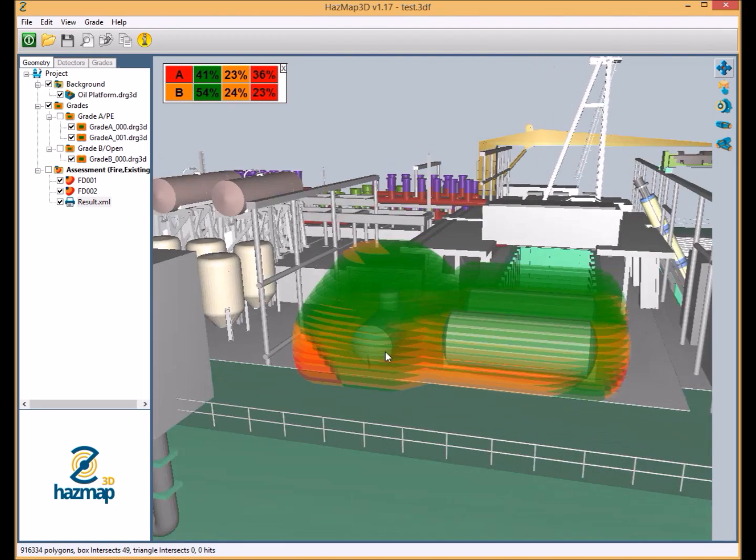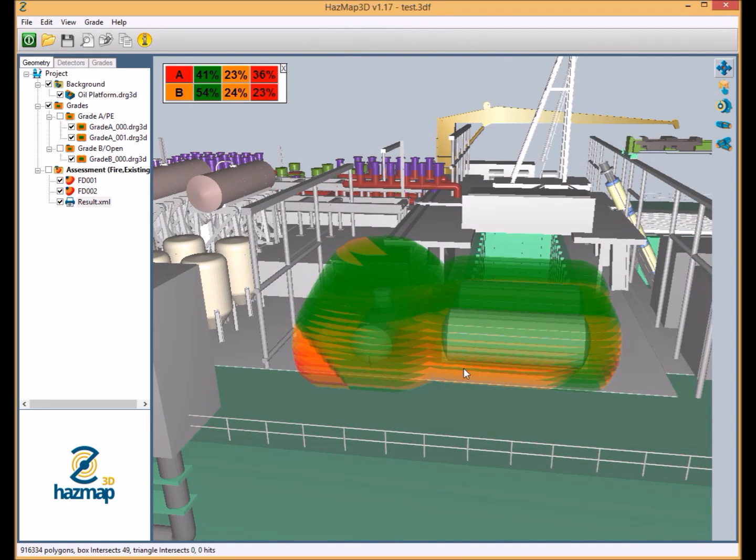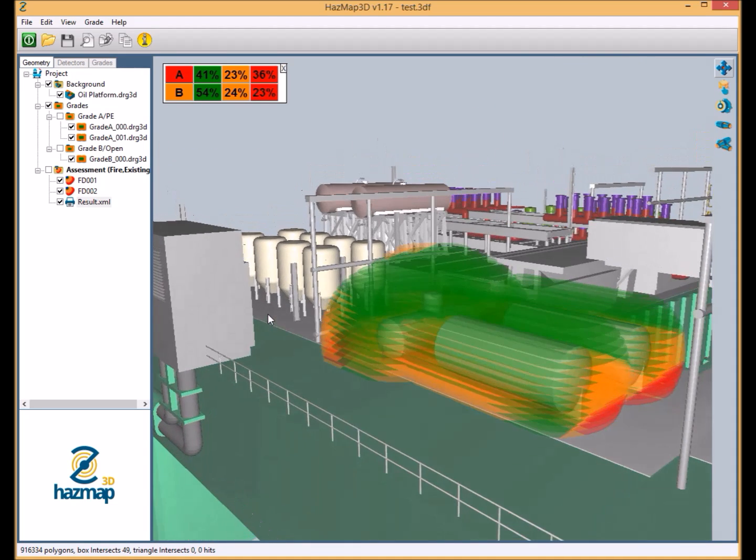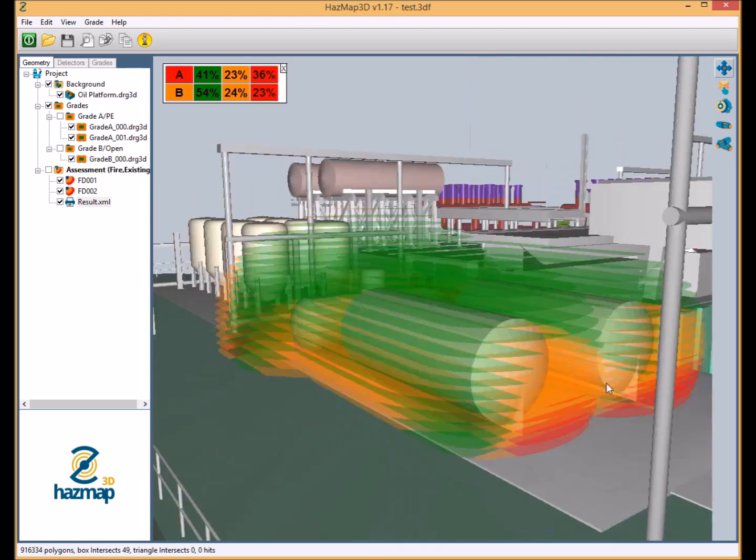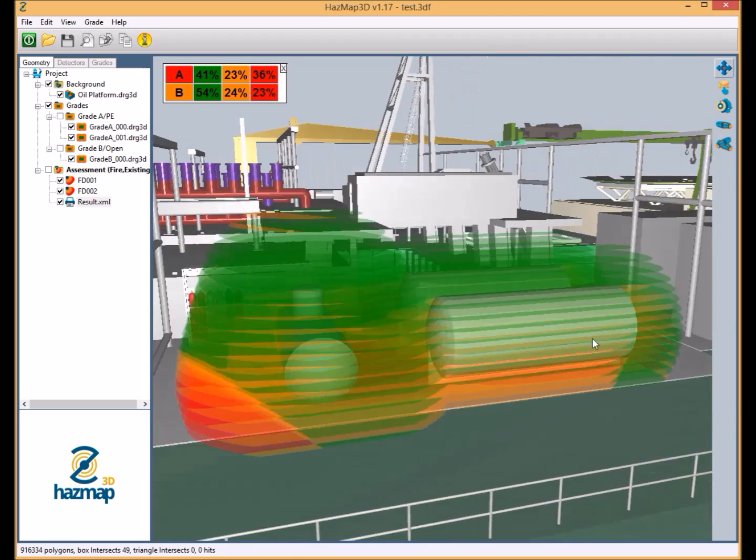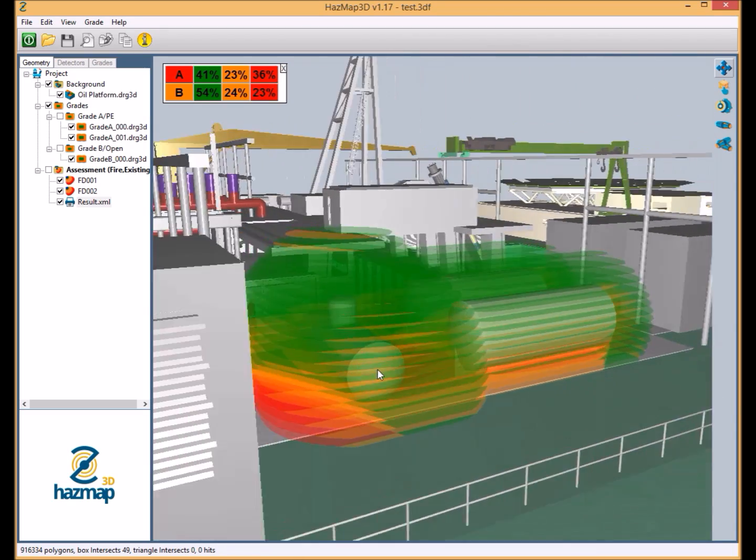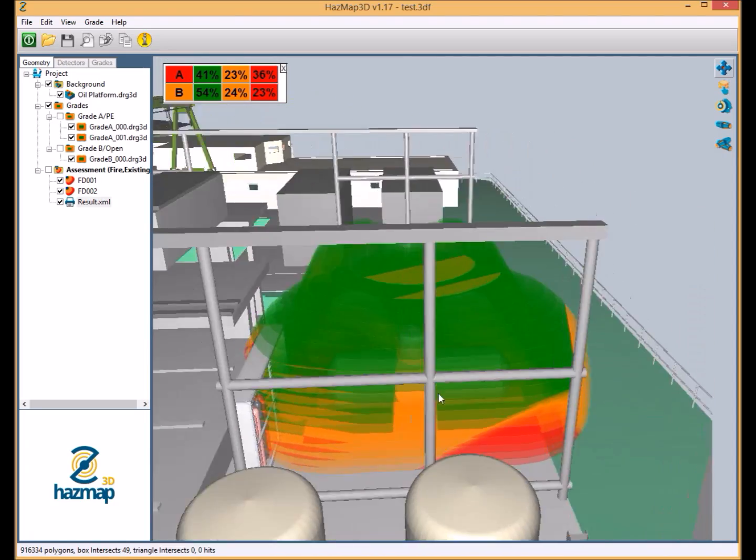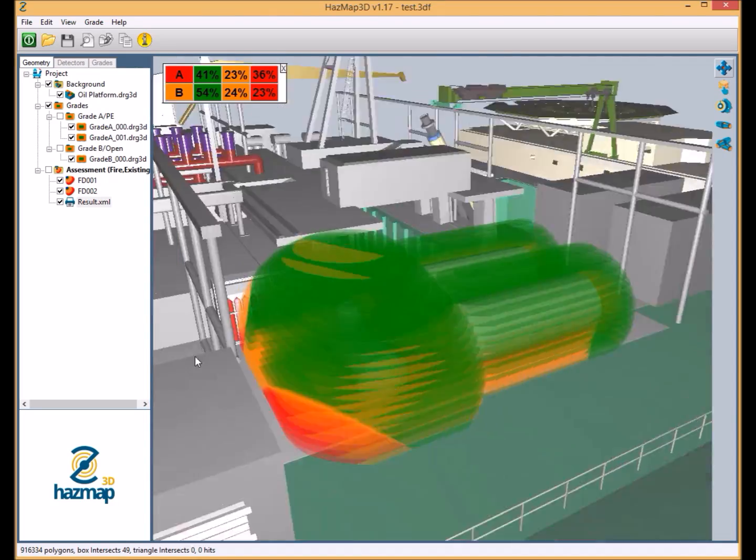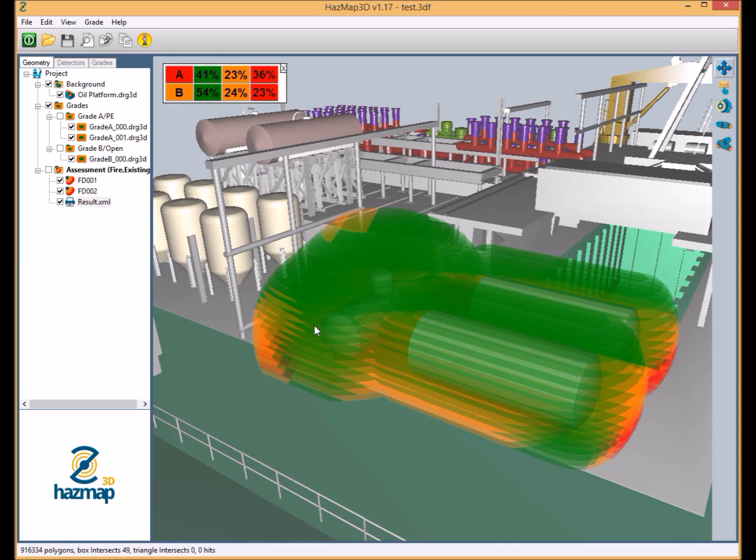So to very quickly run through what these colors mean: we have green for 2 out of n coverage where also the target fire size has been detected by both detectors and that's for both alarm and control action. What the orange represents is our alarm only coverage where only one detector can detect the target fire size. And obviously our red stands for the blind spots where neither detector can detect the specified target fire size.